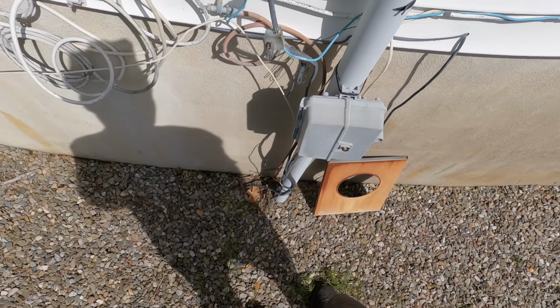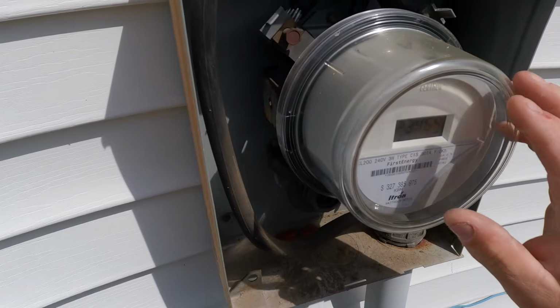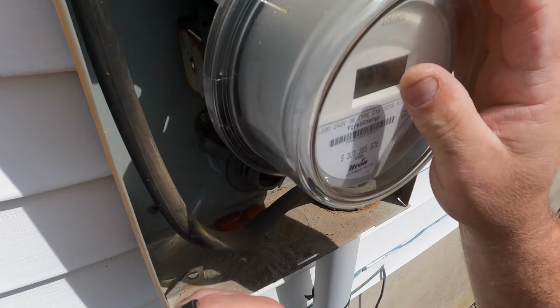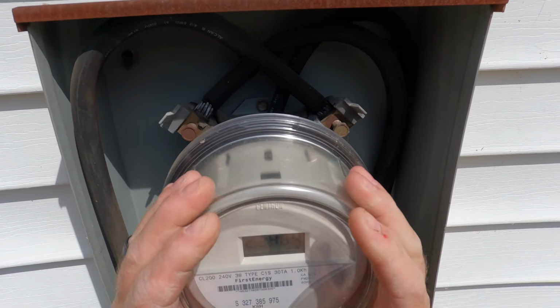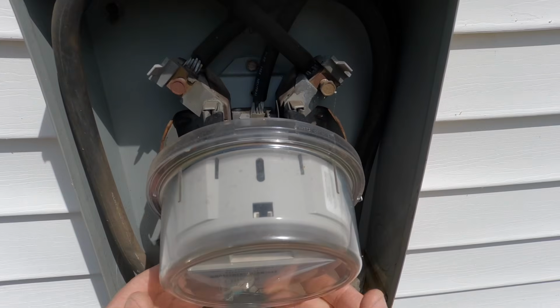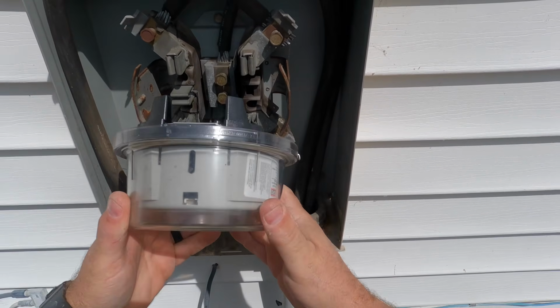So as with any panel change or upgrade or service upgrade, we want to turn off the main breaker and all the individual breakers before we pull the meter so we don't have any arcing going on.